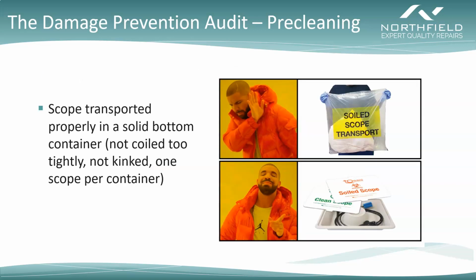Now, one of the most common sources of preventable damage happens during the transportation phase. We want to make sure that the scope is being transported properly in a solid bottom container that is the right size so that you do not have to coil the scope too tightly and that you don't kink it. One of the most common mistakes we see is having more than one scope put into a single container. This happens a lot, especially when you're doing a double procedure such as an upper and a lower, and you end up just putting both scopes into the container because that seems more efficient, right? You have one container to move. But what happens is that the scope ends up crushing the other scope, and these things are so delicate that it's incredibly easy for any sort of extra weight to do damage.